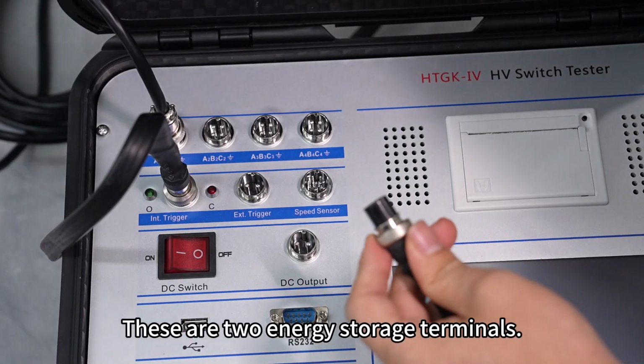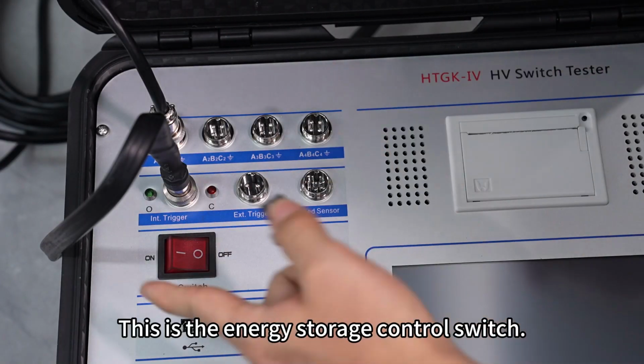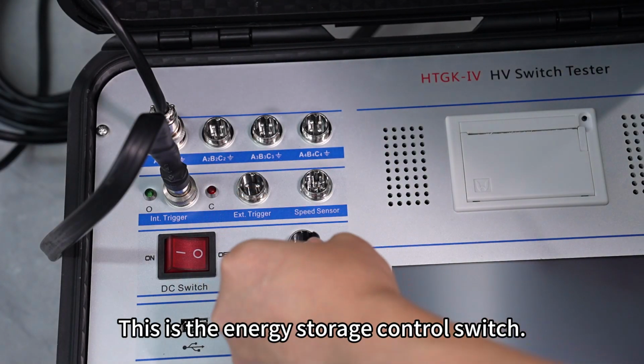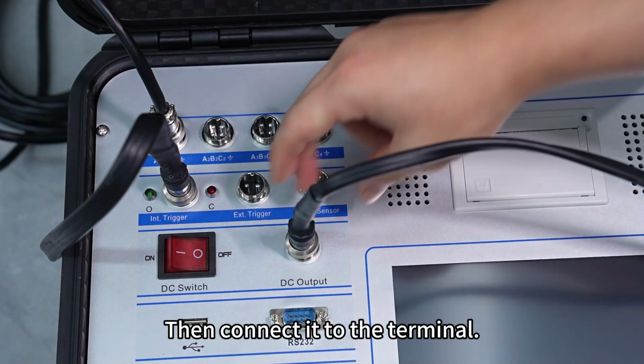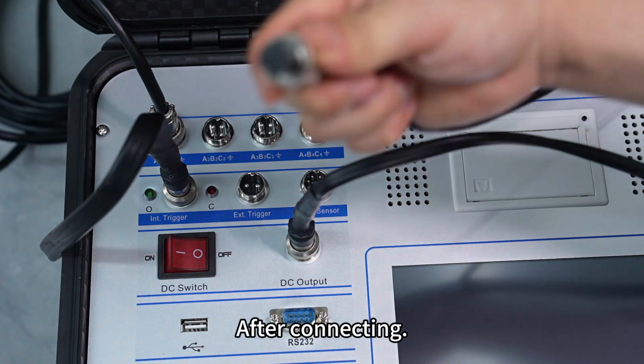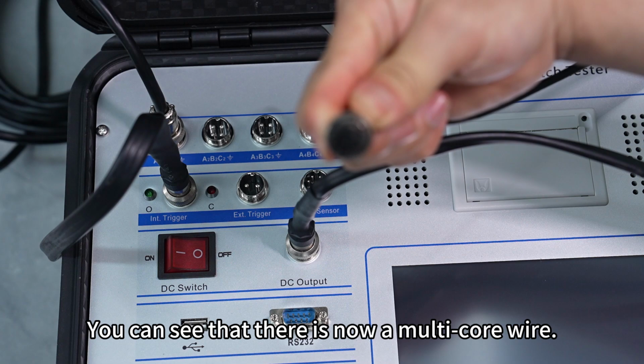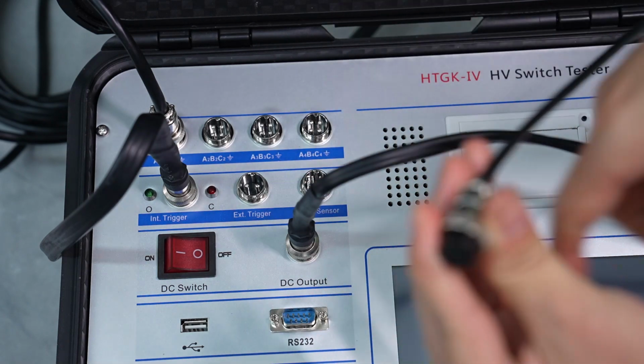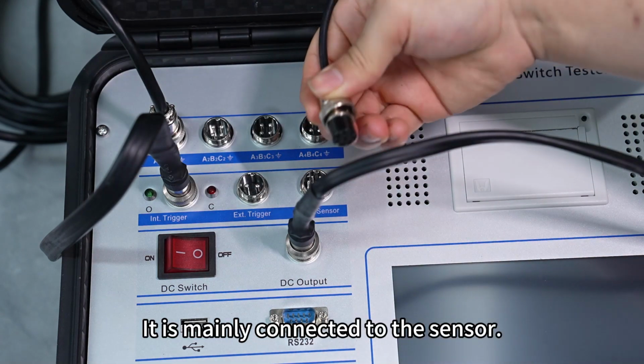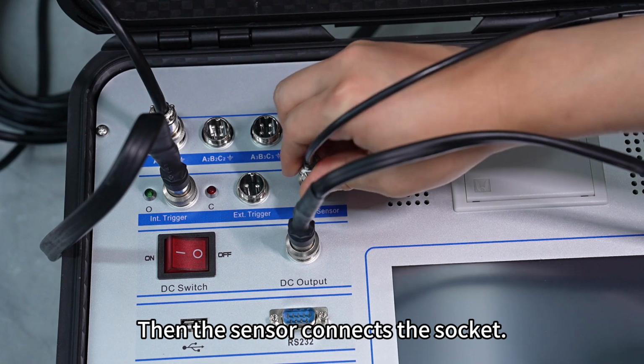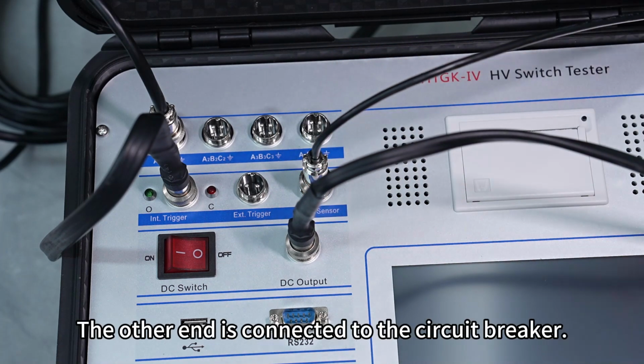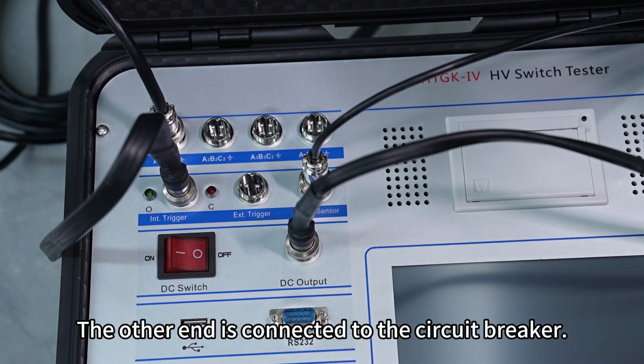These are 2 energy storage terminals. This is the energy storage control switch. Then connect it to the terminal. After connecting, you can see that there is now a multi-core wire. It is mainly connected to the sensor. Then the sensor connects the socket. The other end is connected to the circuit breaker.